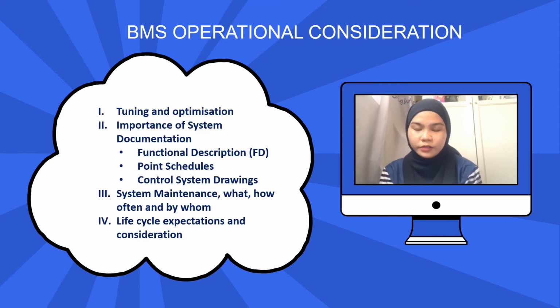Point 3, the control system drawing should include a drawing of the network architecture, detailing the physical wiring connections to the controller, useful for finding faults and establishing spare capacity.